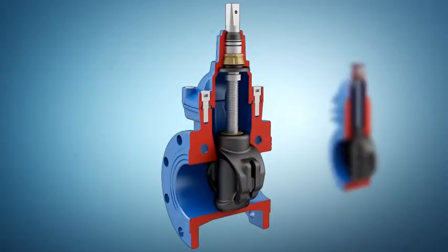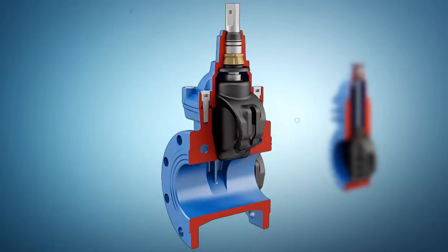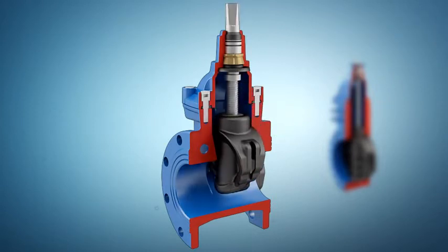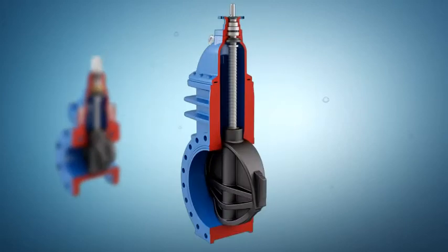Guide rails in the wedge, equipped with wedge shoes, secure smooth operation of the valve. The wedge shoes bring about low operating torques. In DN40-400, the wedge shoes are fully integrated in the wedge to prevent corrosion. In DN450-600, the guide rails are reversed and the wedge is designed with external shoes to keep the operating torques to a minimum.